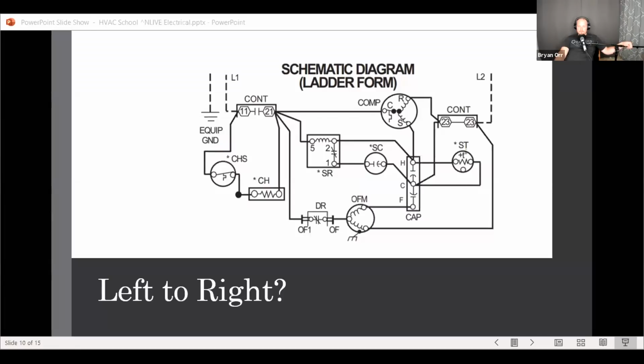Yeah. I'll say one of the biggest things that I see technicians struggling with in diagnosis is troubleshooting to ground, and trying to troubleshoot circuits to ground, and not taking the readings across components to be able to diagnose the component. And I think you went into it there with the measuring across the contactor, and you should have the same voltage when you're looking at that ladder diagram between 11 and 23 and 11 and 21 when that contactor is right. Exactly. Yeah. That's a really good example.